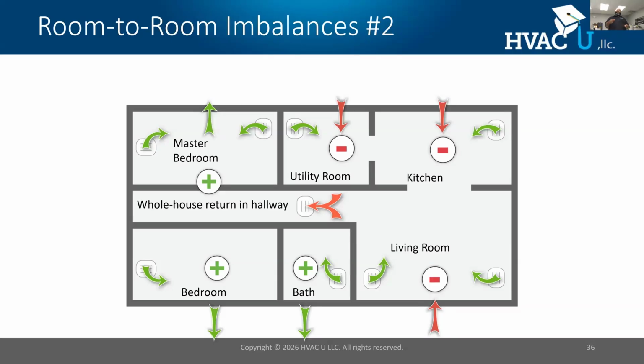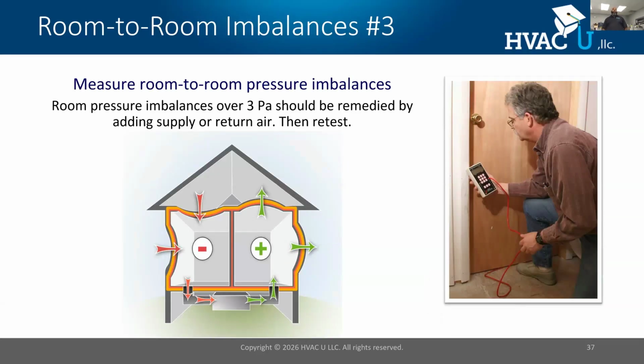So I'm going to compare each of these rooms, and each of these rooms is going to let me know if I have an imbalance. This is important. You may have some customers complain that they become uncomfortable once they close the door. They may have a lack of supply or return air, and we need to identify why. So we have the air handler running. We're going to take a manometer like the technician in this picture does, and we're going to take a tube and compare that room with reference to the hallway or central part of the home.